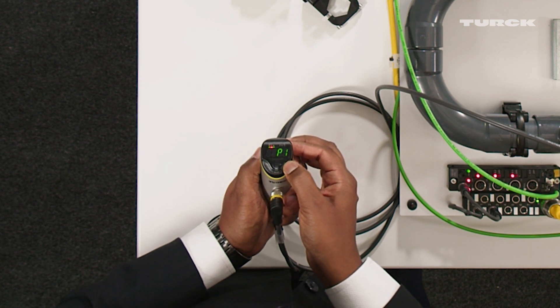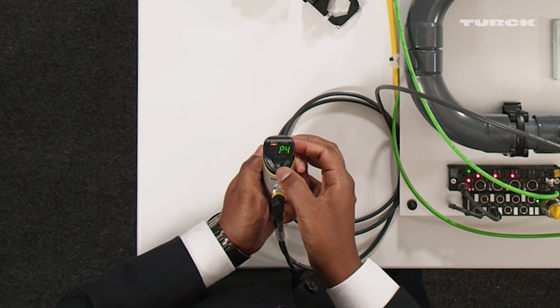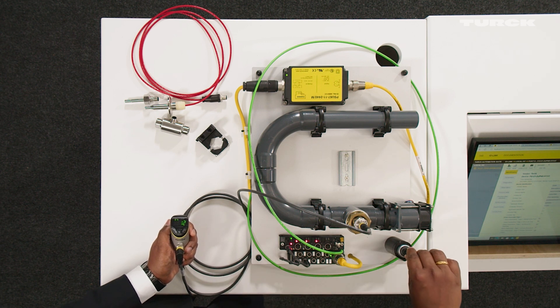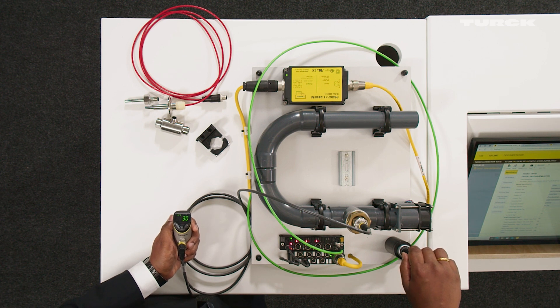Keep set pressed and change to P4, press enter. You see the probe is now connected and the FS1-2-1 is also showing the default values which are meant for the P4 group. By changing the flow rate, you can also see the values displayed on the sensor changing.